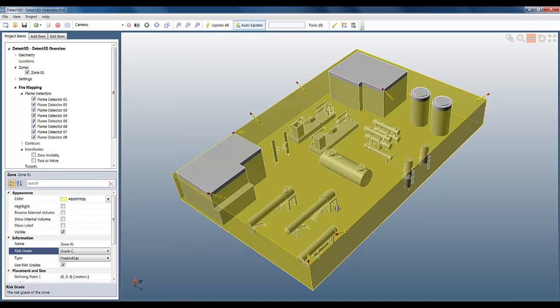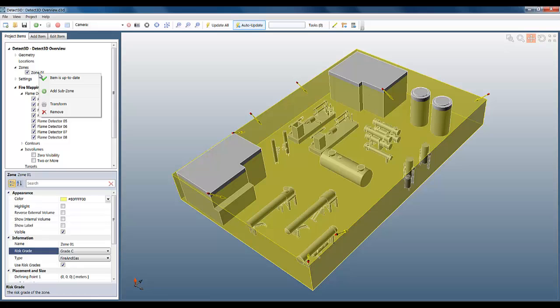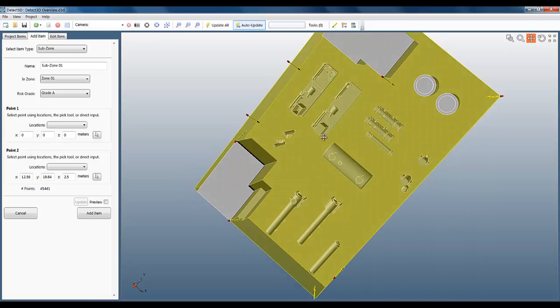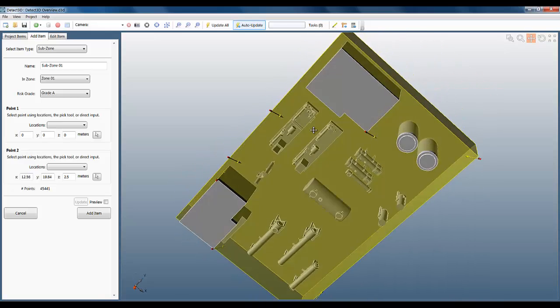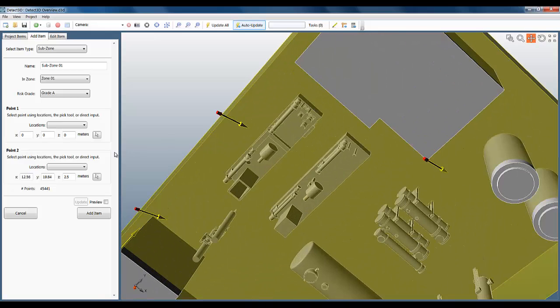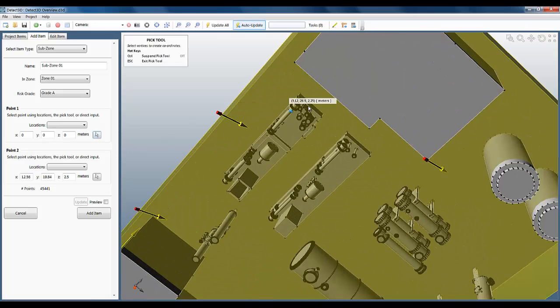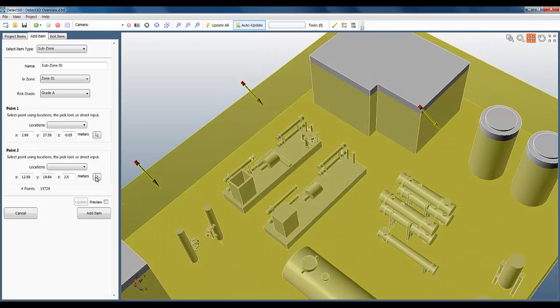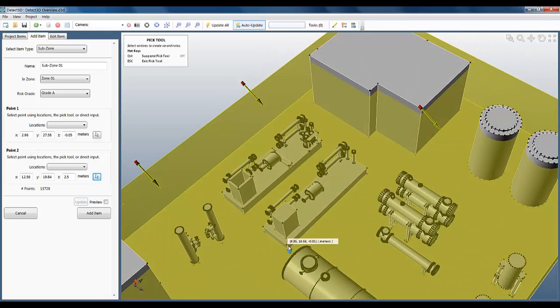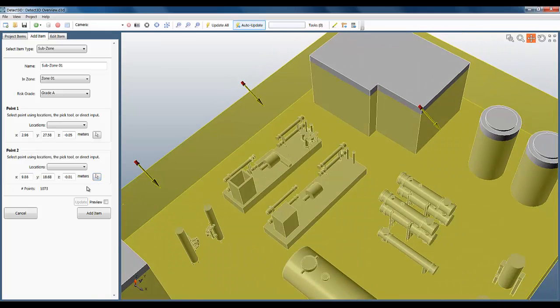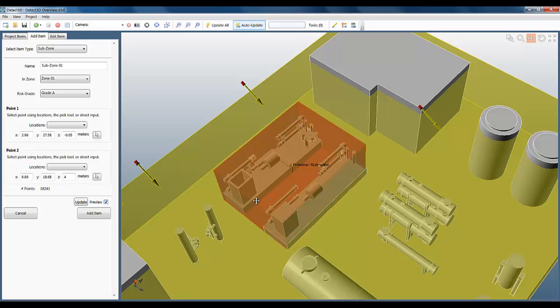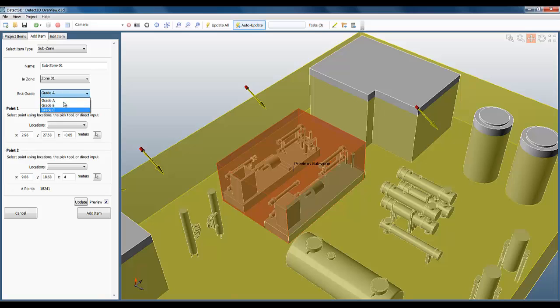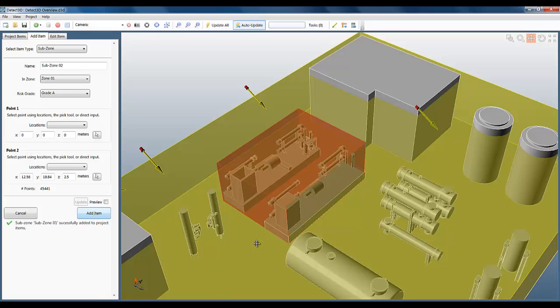Let's define a couple of subzones to mark out some higher risk areas. To do this, I need to select the fire zone, right click, and select add subzone, and use the pick tool to select the points where I want the subzone to be. I can preview the subzone to check it's in the right place and I can also set the risk category, but here it's defaulted to risk grade A, which is what I want anyway. So I'll just add it to the project.